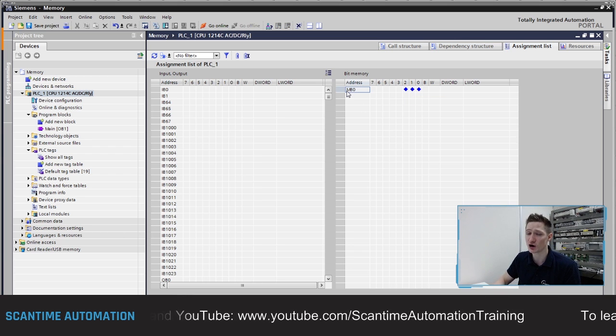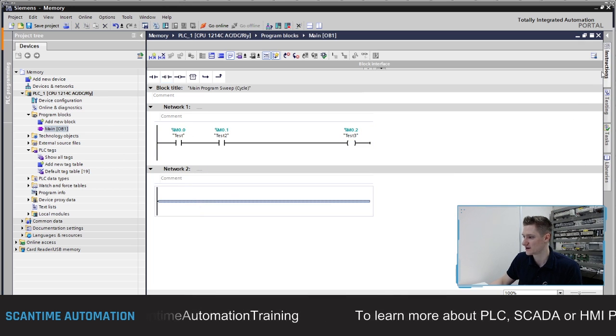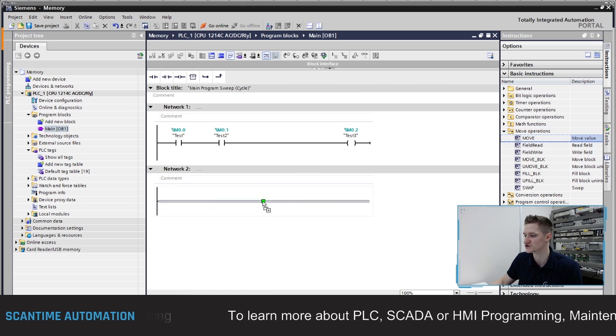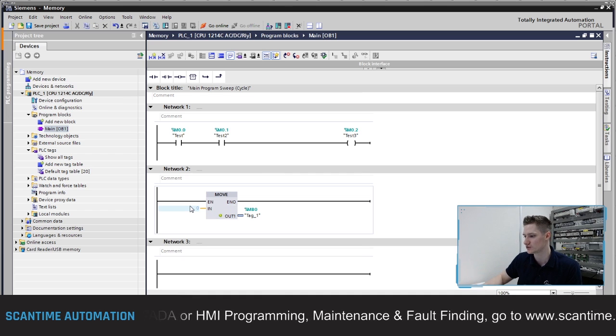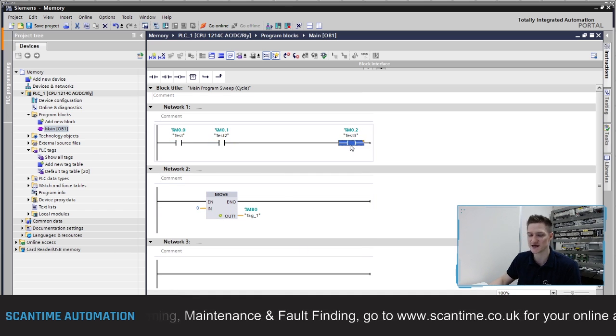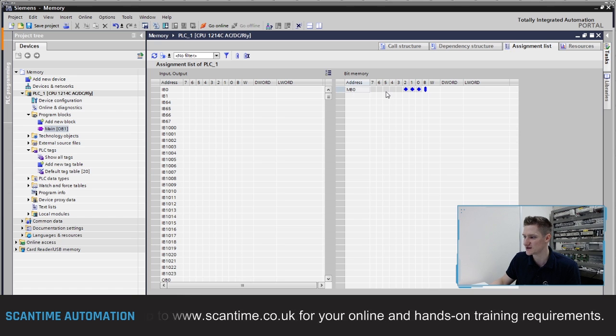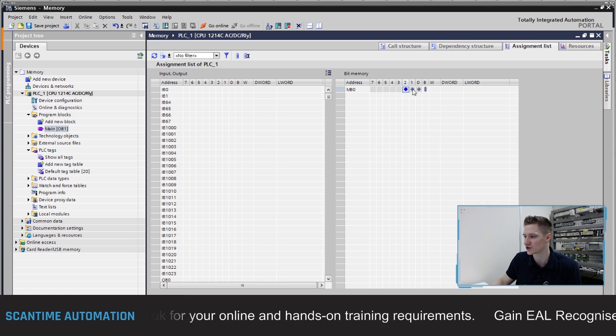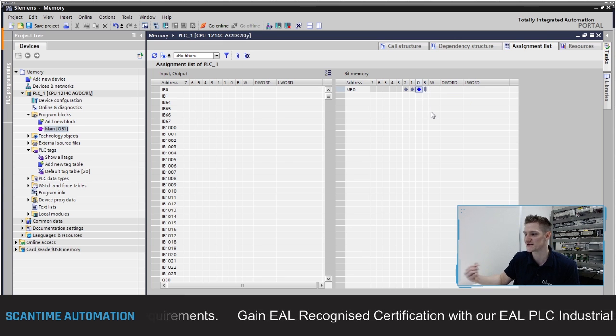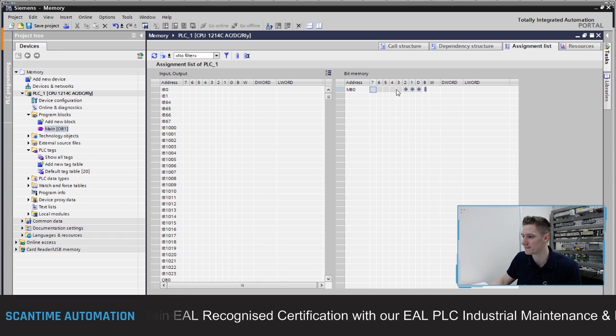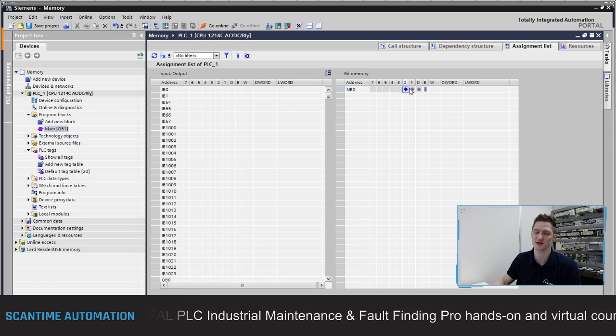Now if we want to use a byte inside the program, I can't use MB0. If I go back to OB1 and insert a Move instruction, moving the value zero into MB0, I am now overwriting these registers inside of the PLC. Looking at the Assignment List now, you can see these areas are shaded out - a darker gray. You can see the little jumper bar on the B column, signifying that we're using a byte MB0 in the program, but we're also using those three bits as well, and that can cause problems.